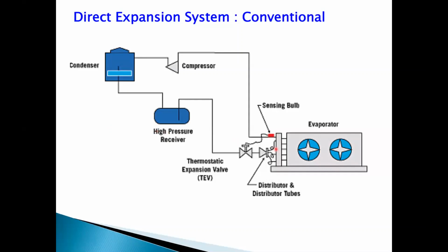Secondly, which part I forgot, there's the superheat. All thermostatic expansion valves operate on 5 to 8 degrees of superheat, and the superheat makes you pay for the energy. The higher the superheat in the gas, the more you pay for energy. But as time evolved, DX systems got replaced by other systems, like the gravity feed system, and then by the pump liquid overfeed systems.